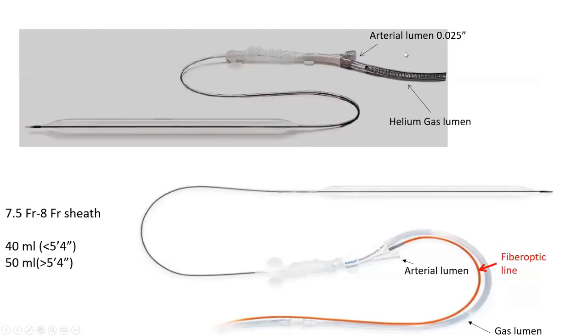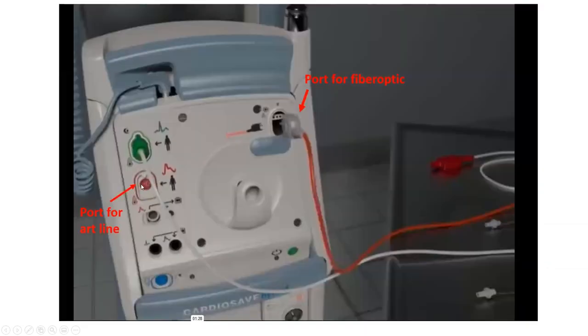You can just connect that line after placing the balloon pump. You can just connect that lumen to a heparin saline bag, and you need to connect it to heparin saline. You want to try to keep that lumen open, not clotted, to prevent clot formation at the tip of the catheter. So you can just connect it to a transducer and to a heparin saline line. You don't need to connect it to the console, although you can. You can connect it using another cable, a special cable that comes with the machine, and that can be connected to that port, but you don't have to.